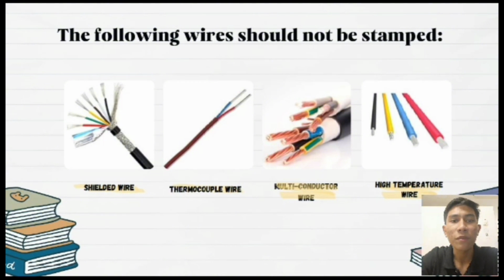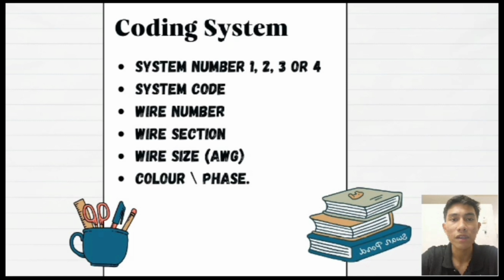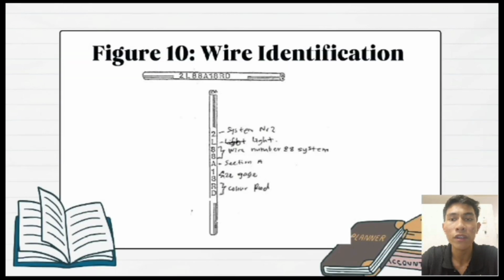As you can see in the picture, there are shielded wire, thermocouple wire, multi-conductor wire, and high temperature wire with insulation difficult to mark. The coding system has 6 parts: system number 1, 2, 3 or 4, system code, wire number, wire section, wire size and color of phase. As you can see, this is an example of wire identification.